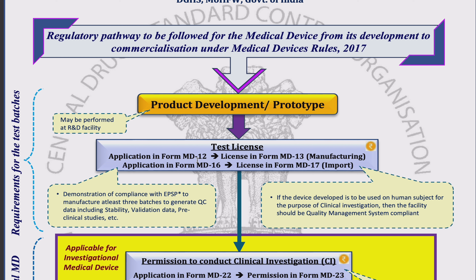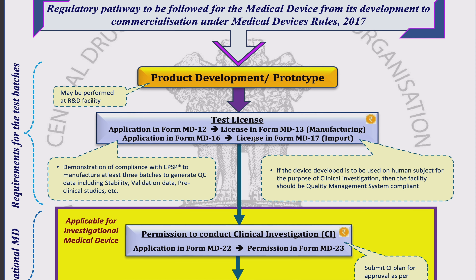When we apply in form MD12, CDSCO is going to grant permission to produce a certain amount of test batches, and they will issue the permission in form MD13. But for import, if a company has a medical device to import, they are not supposed to file a test license in form MD12; rather, they need to apply the application in form MD16, and CDSCO is going to grant the permission in form MD17.